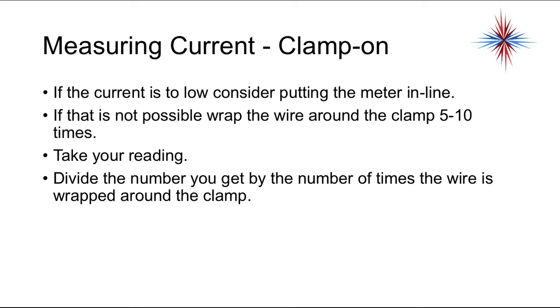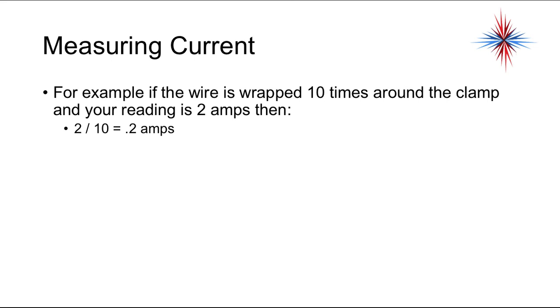If the current is too low, consider putting the meter in line. If it is not possible, wrap the wire around the clamp 5 to 10 times, take your reading, and divide the number you get by the number of times the wire is wrapped around the clamp. For example, if the wire is wrapped 10 times around the clamp and you read 2 amps, then 2 divided by 10 is 0.2.